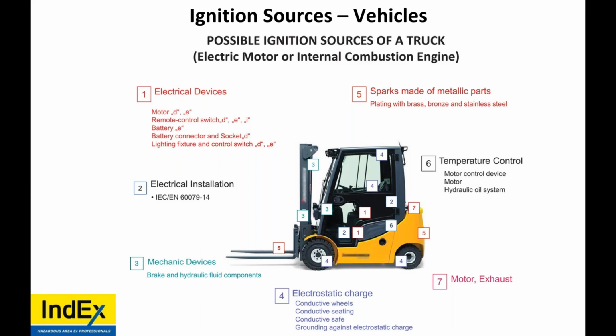would you possibly consider the possible ignition sources on a vehicle, whether it be electric or internal combustion? Well, the motor needs to be EXD or E, the remote control switch has to be EX, the battery has to be EX, the battery connector and socket have to be EX, the lighting and control systems have to be EX. The electrical installation is a potential ignition source. It has to be EX. Mechanical devices such as brakes and hydraulic fluid components are another potential source of ignition. It has to be EEX.